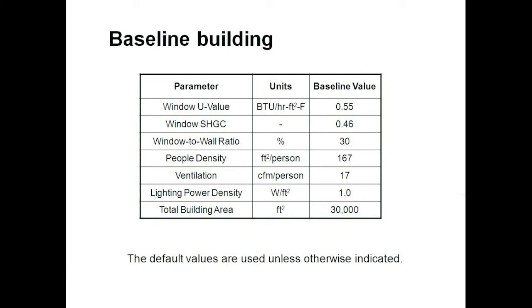The window solar heat gain coefficient is a value of 0.46. The window-to-wall ratio will be set to 30%. The people density of an office is approximately 167 square feet per person, and the ventilation rate for those occupants is 17 CFM per person. The lighting power density established by code for an office building is 1 watt per square foot. And this office building is 30,000 square feet.